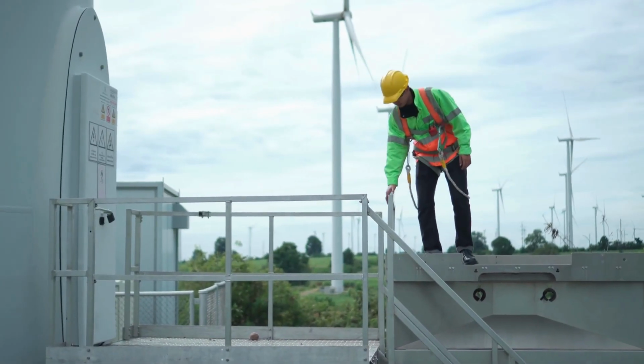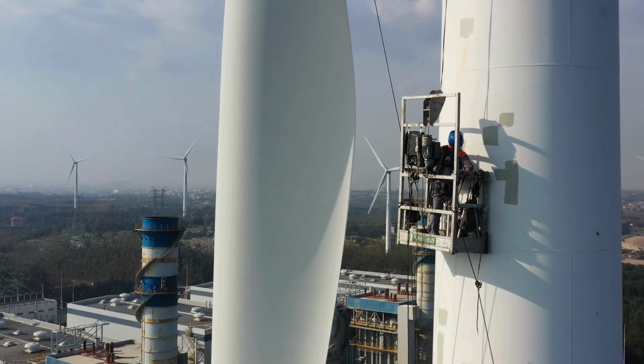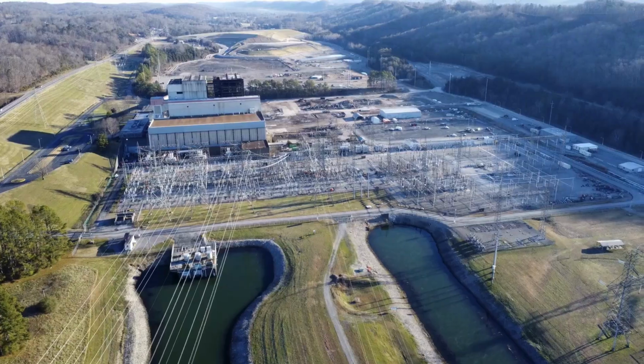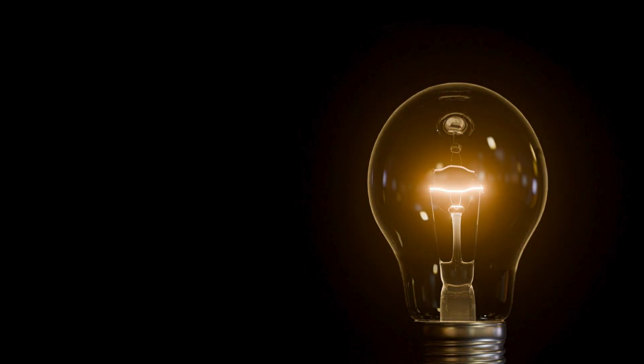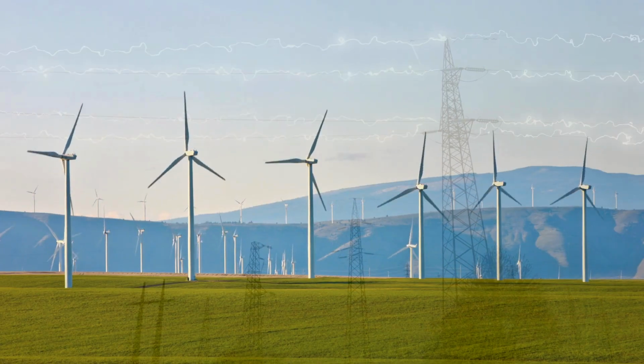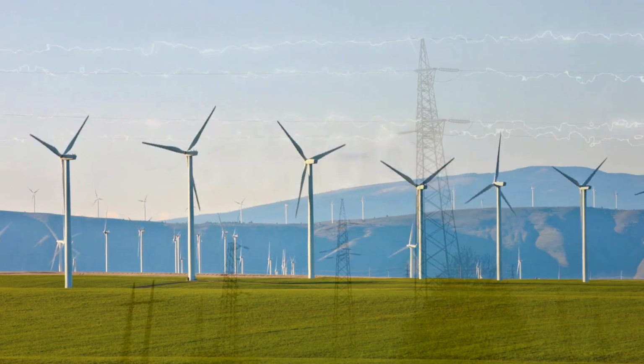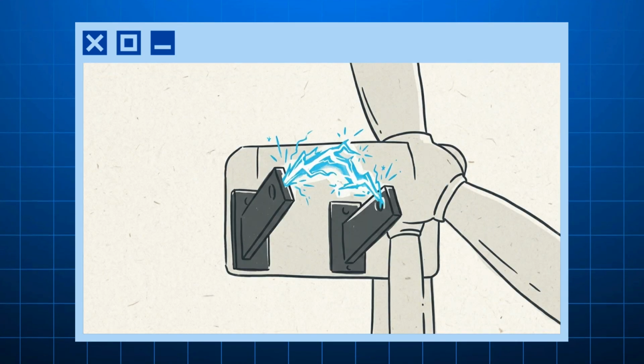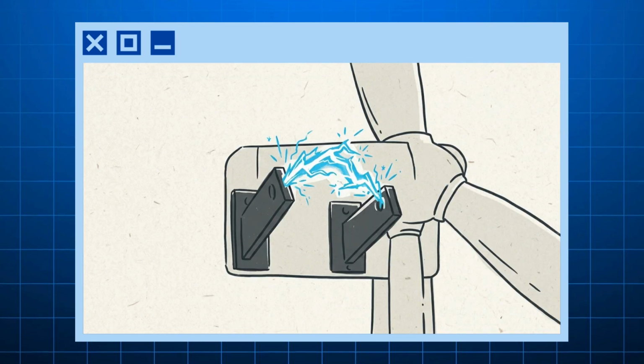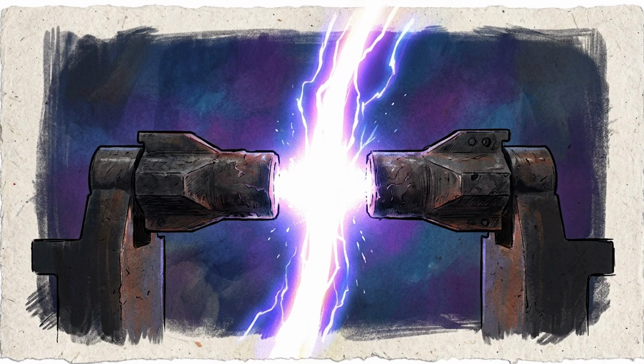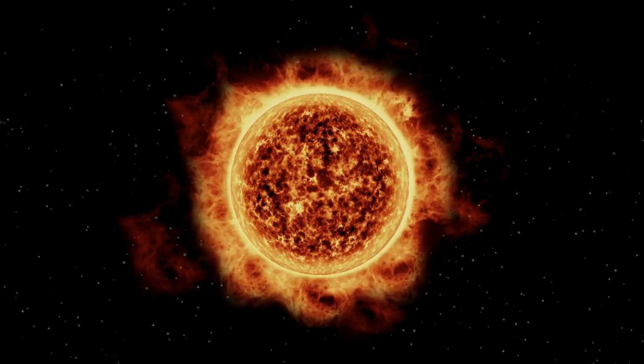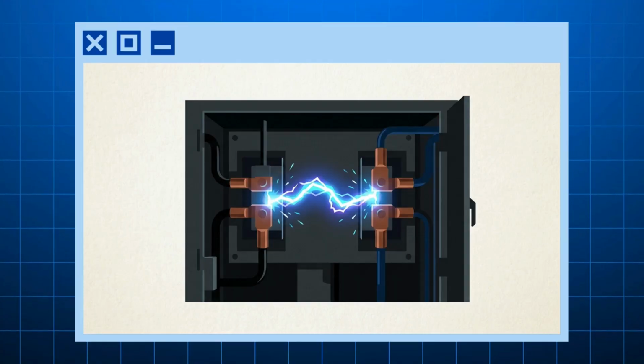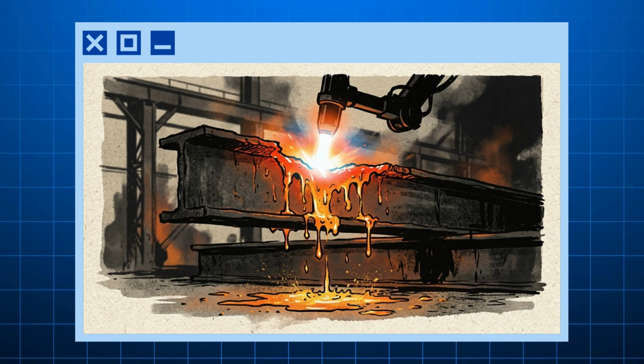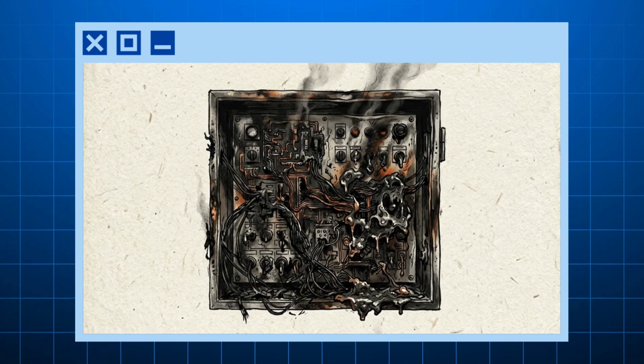To understand why engineers deliberately put this super pollutant inside our greenest machines, you have to look at the immense voltages required to run a modern power grid. A standard household light switch is simple because the voltage is low enough that air easily stops the current when the contacts separate. But a modern wind turbine operates at up to 66,000 volts. At this scale, when you switch the power off, the electricity jumps. It tears through the air, creating a blinding plasma arc that burns at over 20,000 degrees Celsius, hotter than the surface of the sun. Without an immediate way to quench this arc, it will vaporize copper, melt steel, and destroy the entire control system in milliseconds.